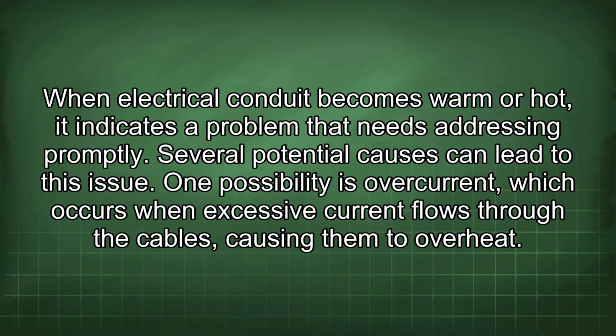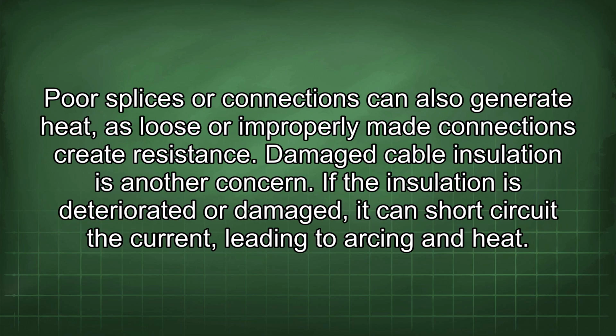When electrical conduit becomes warm or hot, it indicates a problem that needs addressing promptly. Several potential causes can lead to this issue. One possibility is overcurrent, which occurs when excessive current flows through the cables, causing them to overheat. Poor splices or connections can also generate heat, as loose or improperly made connections create resistance.